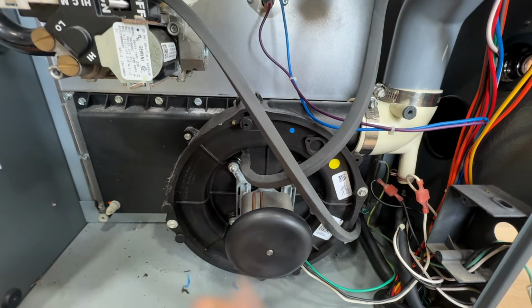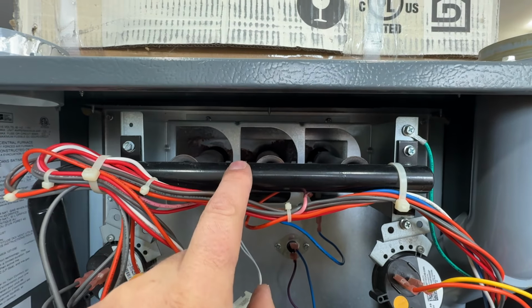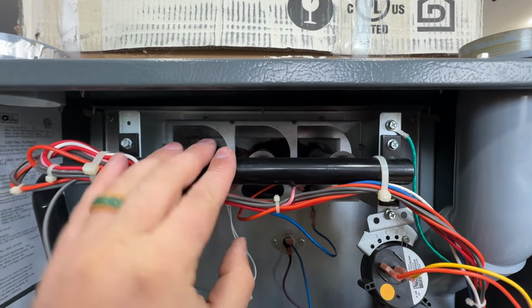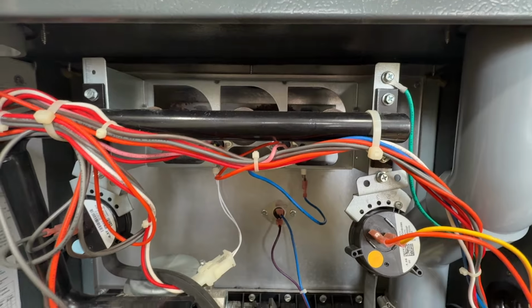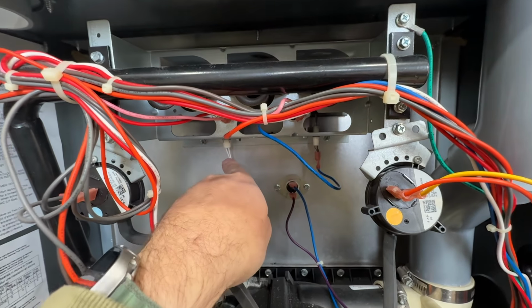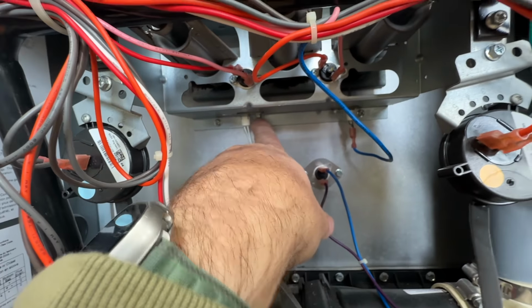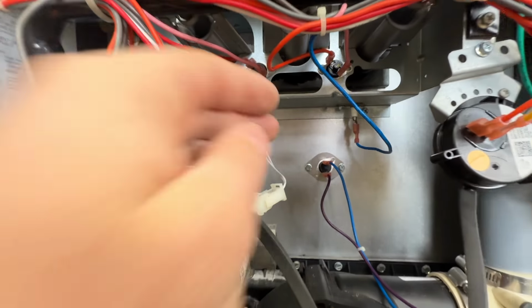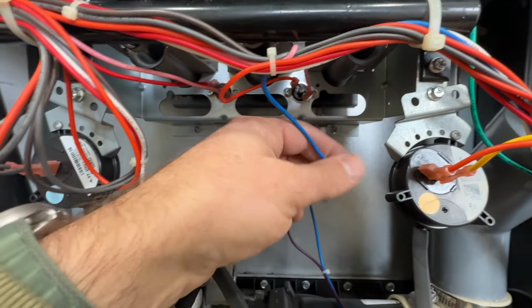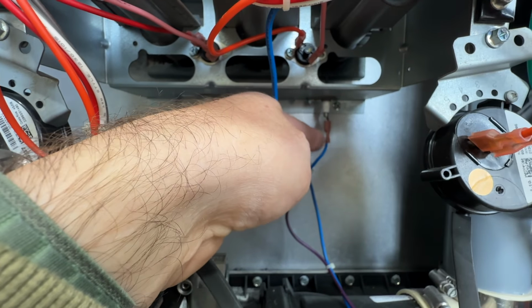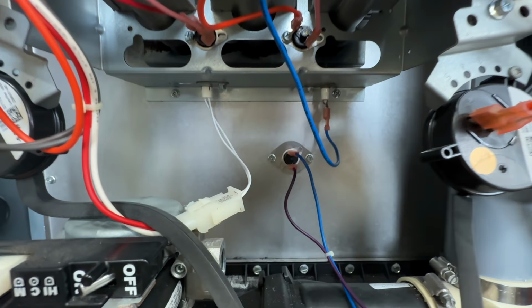Now, if you go down to your furnace and you hear the inducer running, but you never see that orange glow, then you know that there's an issue. The spark igniters rarely go bad. It's mainly these hot surface igniters that go bad. So I'm going to show you what they look like. It's just one screw, and it typically has 2 wires. The one that has one singular wire, that's, as we talked about before, that's going to be your flame sensor.